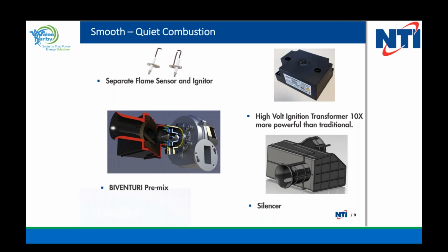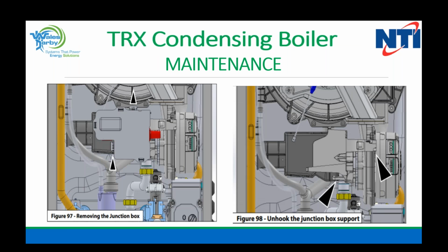But the maintenance here is pretty simple. We should have a couple of slides to show that. So you open up and you remove the junction box, so that black triangle is showing you where the junction box connections would be. Then you unhook the junction box support, as you can see there on the right-hand side. Next, yep, John's going to use the highlighter to show that. Okay. Now all the wiring is Molex plugged in, so as you go to the next slide, John.